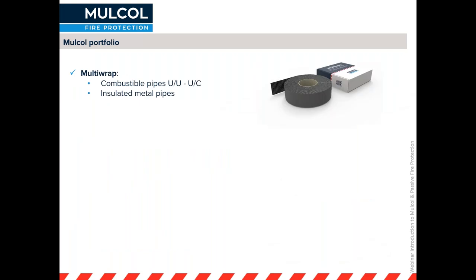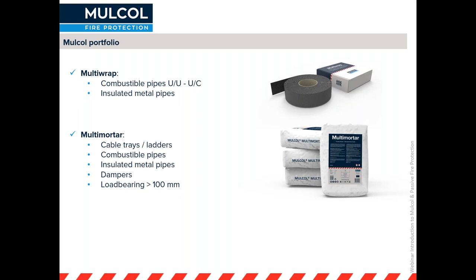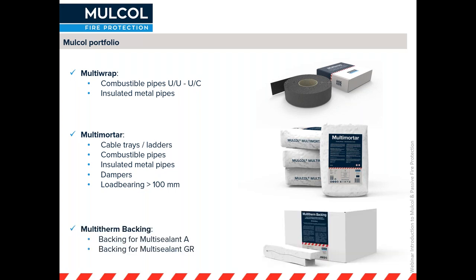Then we've got the Multiwrap, which is a wrap mainly for combustible pipes and insulation around metal pipes, and the Multimortar. This Multimortar can be load-bearing if it's used over 100 millimeter thickness, and it's used mainly with the things you find, for example, in risers like cable trays, dampers, combustible pipes, etc. And the Multi-Therm backing for our Multisealant A and for our graphite sealant as well.